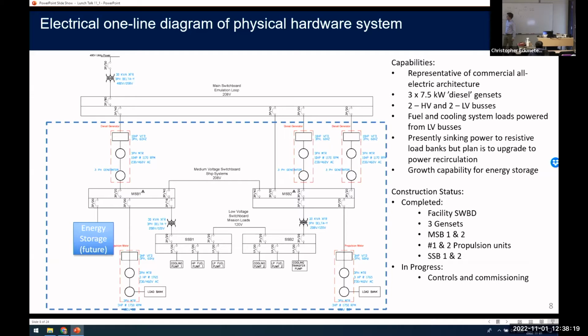With the three-phase input feed, we feed generators. These generators aren't physical generators burning diesel, because that would be unsafe and hazardous to have in the building, and it doesn't allow us to trigger the complexity of faults and failures without doing it once and then having to replace an entire diesel engine. We chose to model a diesel engine with a variable frequency drive fed by the utility power and a three-phase induction motor. So we have an electrical three-phase machine with a control loop spinning another electrical three-phase machine that's generating electricity again. If that makes sense.